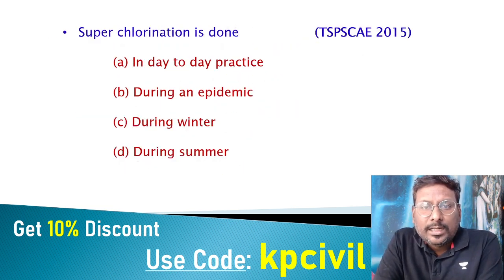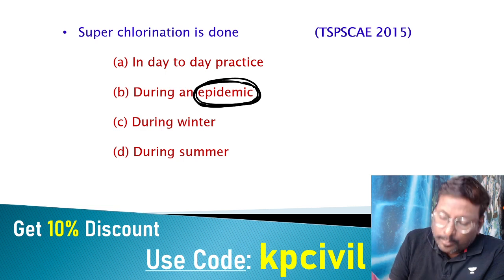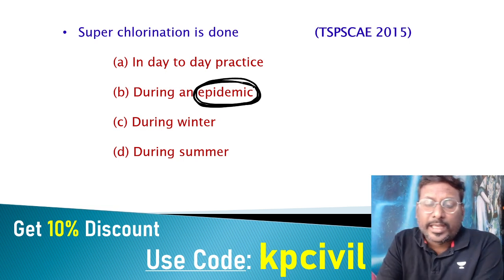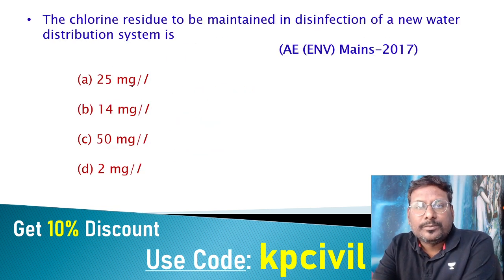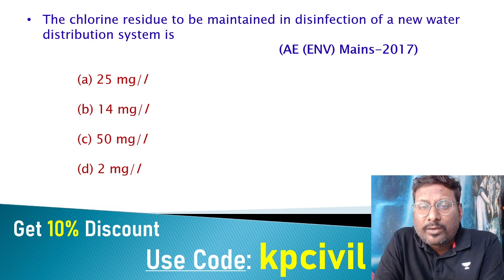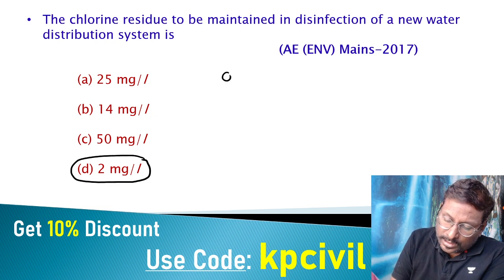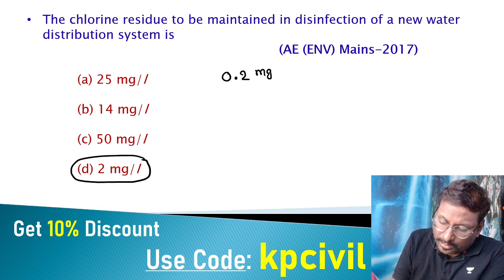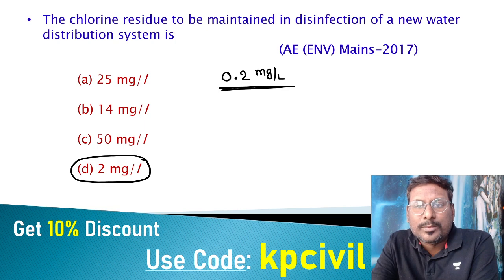Super chlorination is done during an epidemic — when a waterborne disease is spreading. For disinfection of a new water distribution system, chlorine residue to be maintained is 2 mg/L. Generally we take 0.2 mg/L, but a new distribution system needs a higher amount of chlorine residue — that is why 2 mg/L.